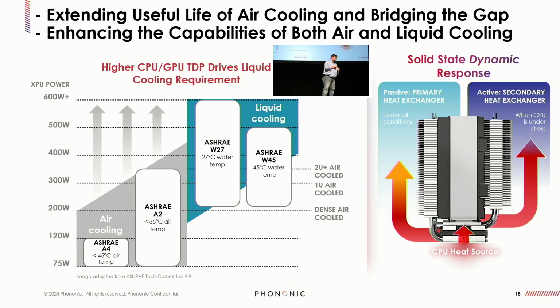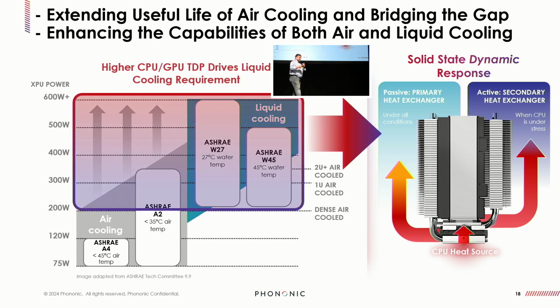But if you have dynamic cooling, what you enable is an enhancement to air cooling. You increase the viability of that air cooling so that you can support significantly more total dissipation, significantly more compute power. But at the same time, you bridge this gap between existing infrastructure, air-cooled, new infrastructure, water-cooled.